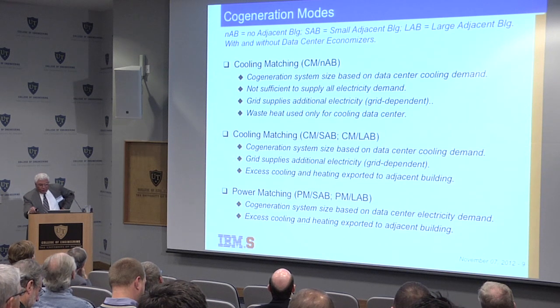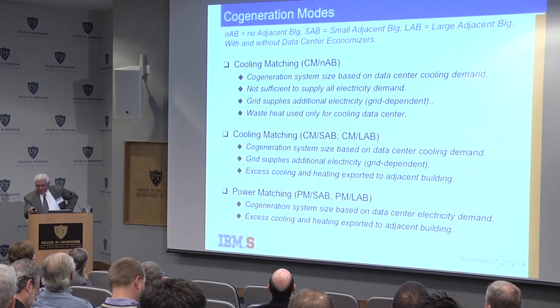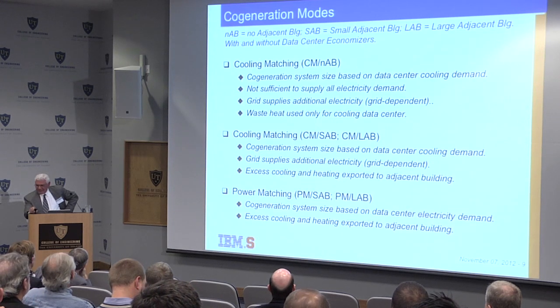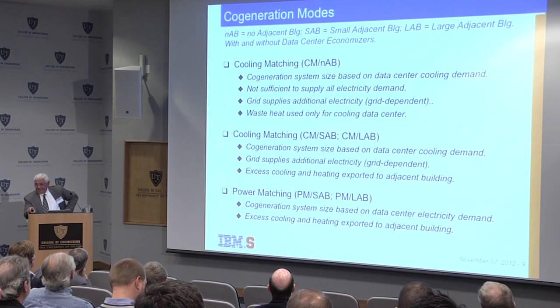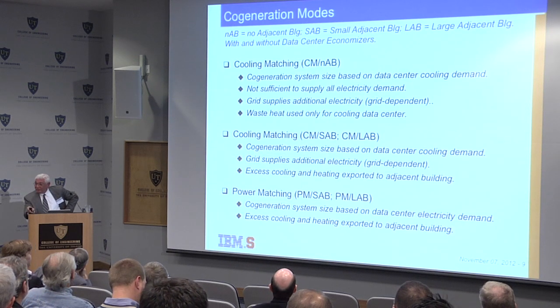So one of the issues with cogeneration systems is you cannot just compute their performance and economics based on design points, because there's always the issue of how much of the waste heat can be used. And how much of the waste heat can be used depends a lot on the weather, which is a time-dependent situation, and also depends on the nature of the load in the building.